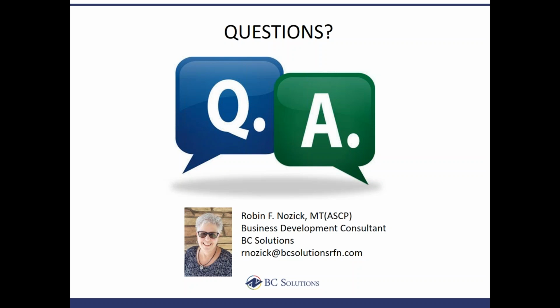By then you should have that testing done, because if you need to change the configuration in your blood bank software, you will need to reconsider what needs to be revalidated, and it's more intensive to do a revalidation than it is to do testing, find out something didn't work, fix it, and retest. So that's what I would recommend.